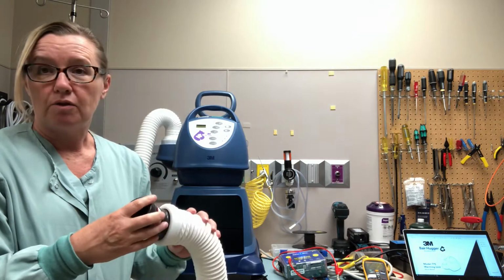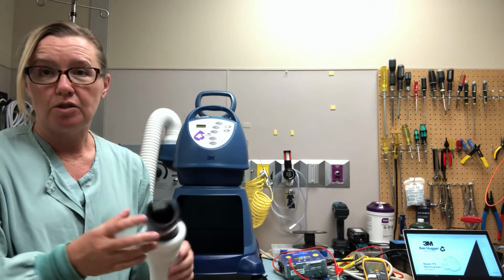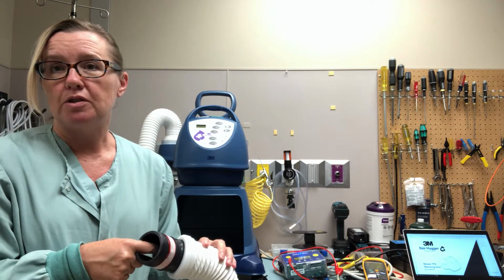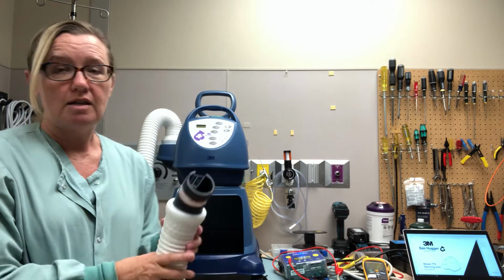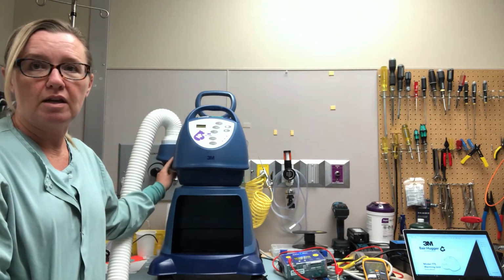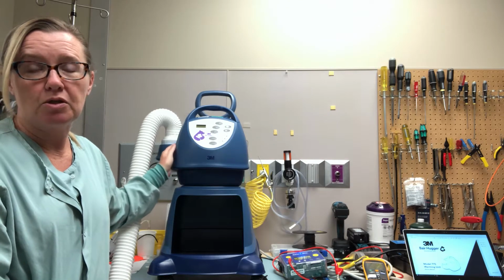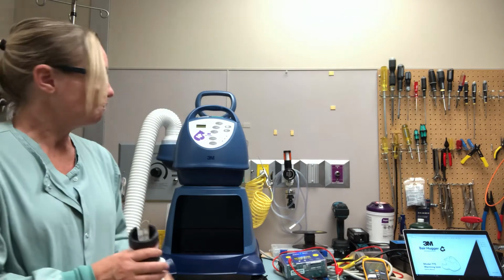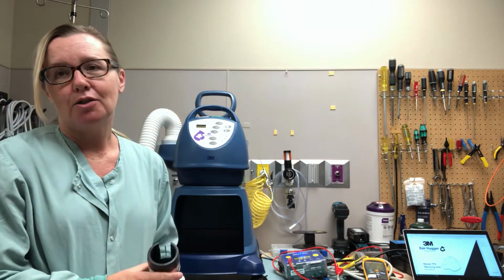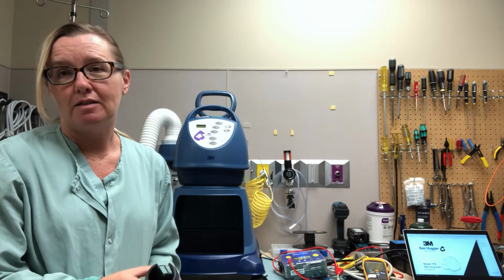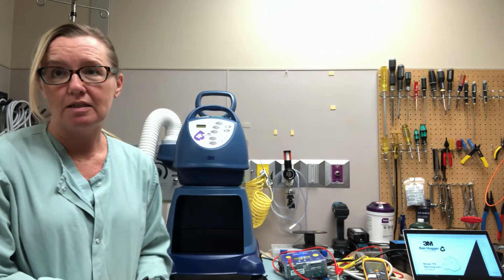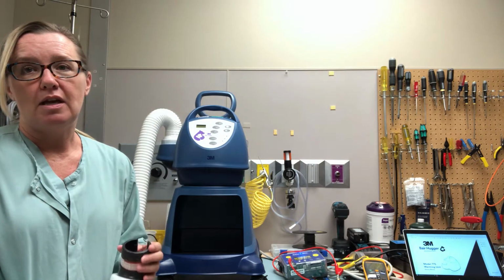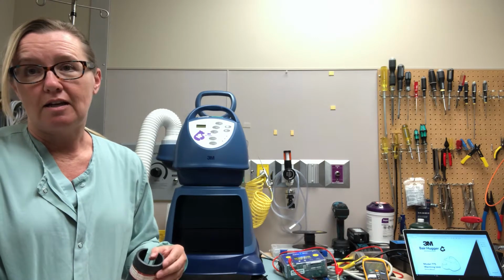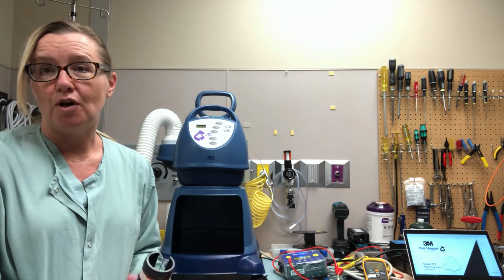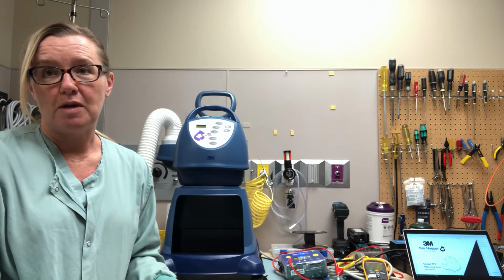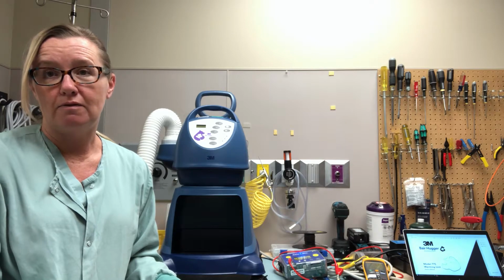So there's several different ways that it's checking the temperature. There are two thermistors in the end of this hose, and then there's one inside this elbow right here. So it's constantly monitoring the temperature. There are a few safety features too. There's an over temperature circuit that will alarm if it gets above anywhere between 46 and 56 degrees Celsius. It'll alarm over temp. And there's also a series of faults that it'll alarm for different reasons, and it gives a fault code which you can look up in the service menu and determine what caused the fault.